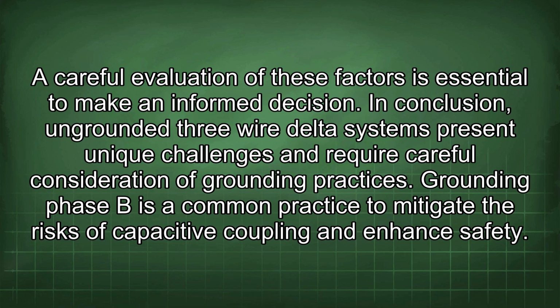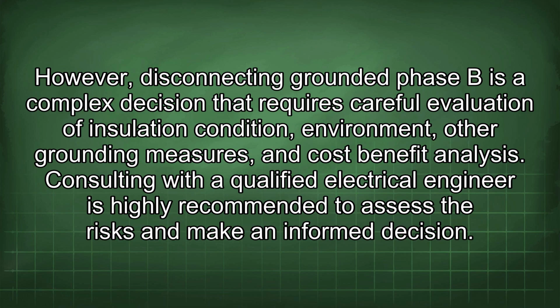In conclusion, ungrounded three-wire delta systems present unique challenges and require careful consideration of grounding practices. Grounding phase B is a common practice to mitigate the risks of capacitive coupling and enhance safety. However, disconnecting grounded phase B is a complex decision that requires careful evaluation of insulation condition, environment, other grounding measures, and cost-benefit analysis.